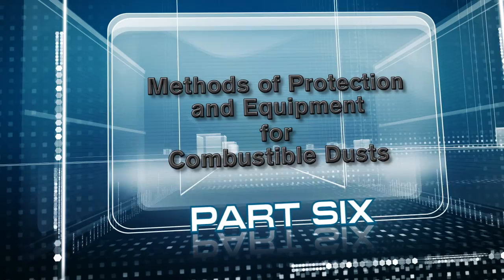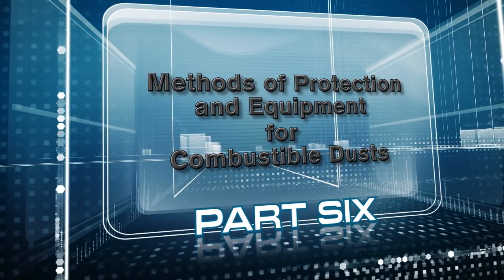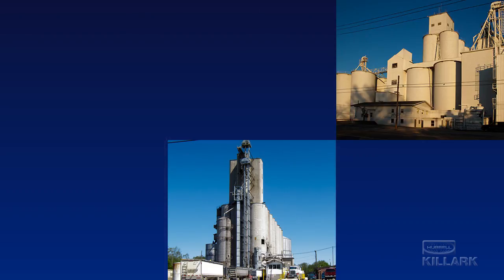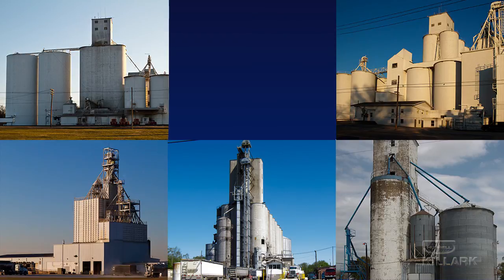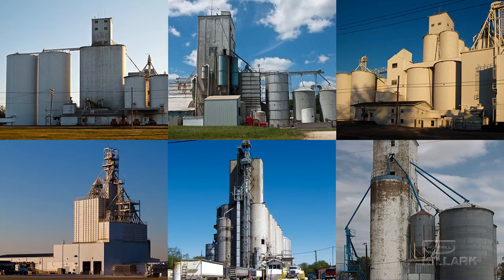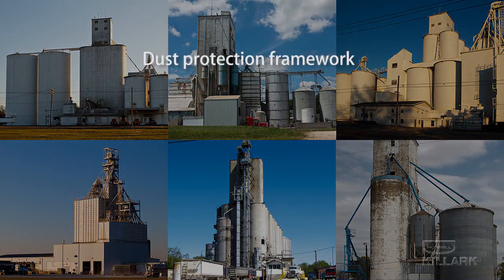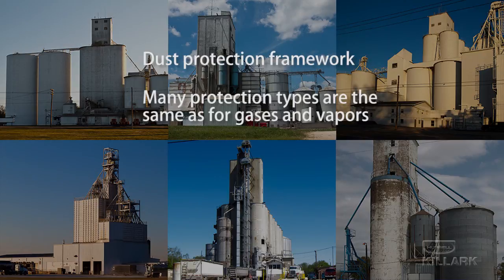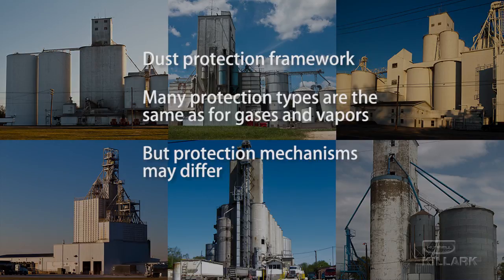Part 6. Methods of protection and equipment for combustible dusts. A framework very much like the one used to explain and label the protection types used for gases and vapors has also been devised for dust environments. In fact, many of the gas and vapor protection types are also available to guard against the risks of dust explosion or fire from fibers and flyings. However, it is important to be aware that the actual protection mechanism may rely on a somewhat different concept for the dust risk than with gas and vapor.